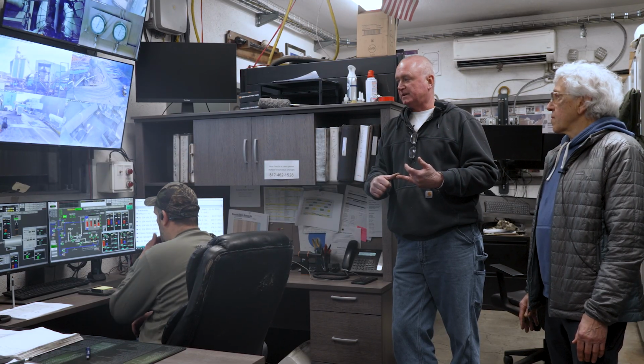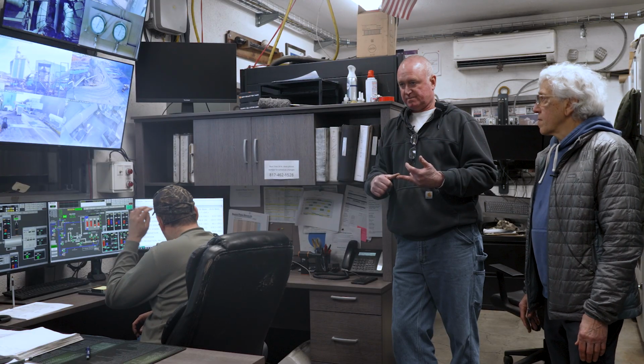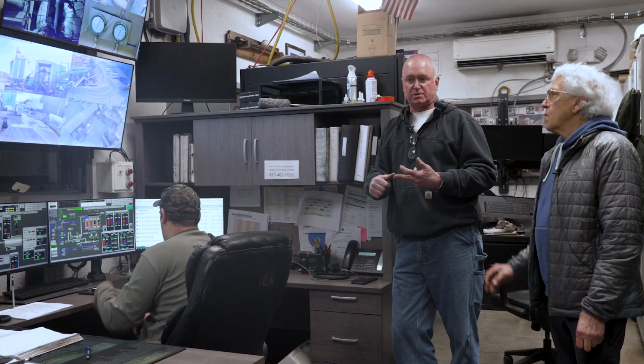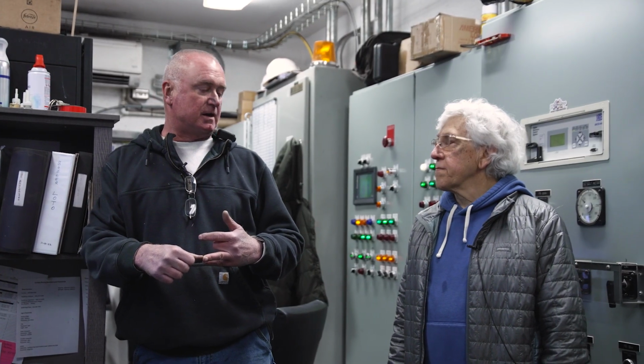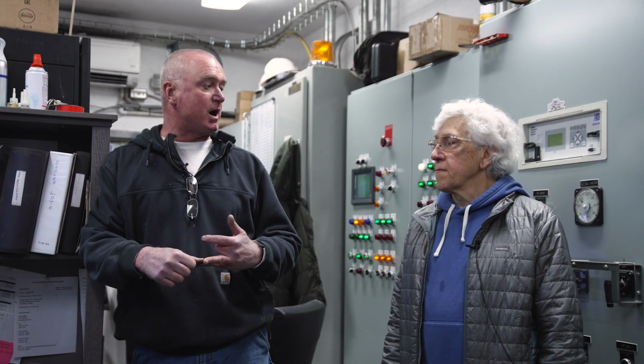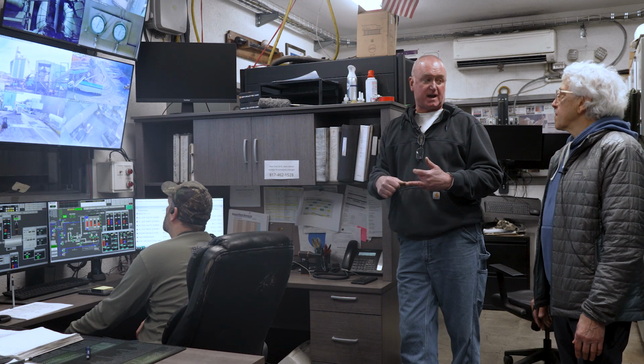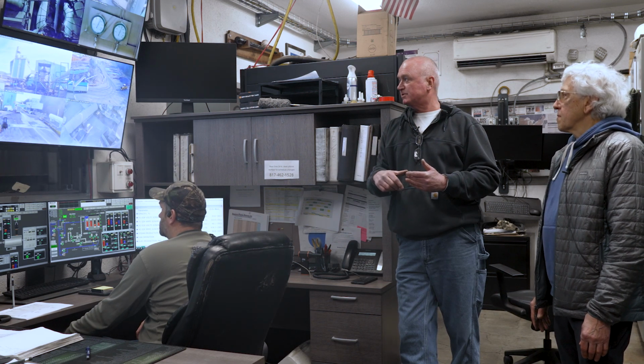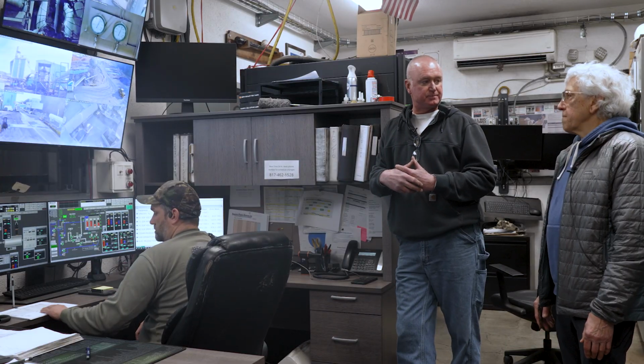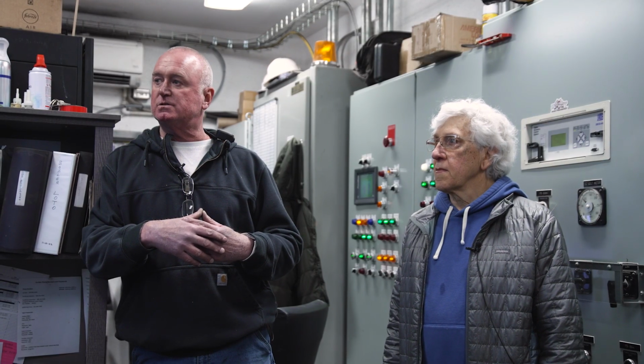That water comes into the facility, goes through a dechlorination system, then an RO, reverse osmosis. Why do you take the chlorine out? Well, chlorine is very abrasive and corrosive when you're talking about boiler tube, especially at the temperatures and pressures that we operate. So we do that to prevent waterside corrosion. There's waterside corrosion, there's fireside corrosion, and we're talking about waterside corrosion with chlorine. We go through an RO, reverse osmosis, which is really just a very stringent membrane filtering system, to purify that water, and then it goes into a 10,000 gallon storage tank.